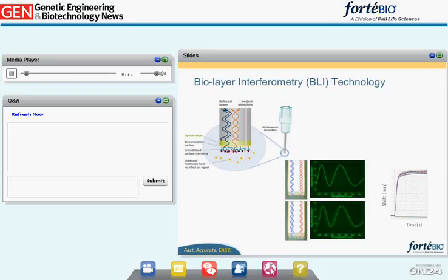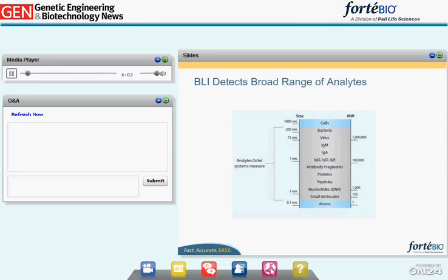This interference pattern is highly sensitive to the distance between the first and second reflections. When analyte from a sample binds to capture molecules on the biosensor, the layer of protein bound to the tip grows in thickness, increasing the distance between the two reflections, manifesting as a change to the interference pattern. This change is recorded in real time up to about 10 times per second. The amount of signal increase is proportional to the number of analyte molecules that bind, and the rate of signal increase can be used to extract binding rate constants and affinity.